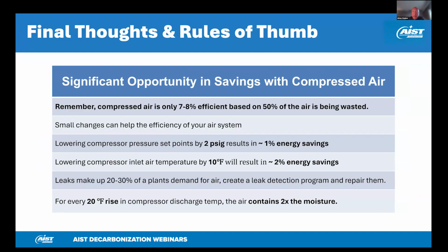So remember, compressed air is not efficient. If there's any way to do anything in your plant not using compressed air, it's worth at least looking into. Small changes can help the efficiency. 2 psi equals 1% energy. So if someone asks you to raise the pressure, it's going to cost you. So let's keep driving the pressure down to save energy. Reducing the temperature will also help. Every 10 degrees is about 2% of wasted energy. So the compressor room temperature is important. Proper ventilation helps. Remember that leaks is about 20 to 30%. So make sure we get a leak program in place. And then the temperature discharge, which comes right as a result of the cooling water, drives up the temperature discharge, which doubles the moisture going to the plant or to the cleanup equipment.